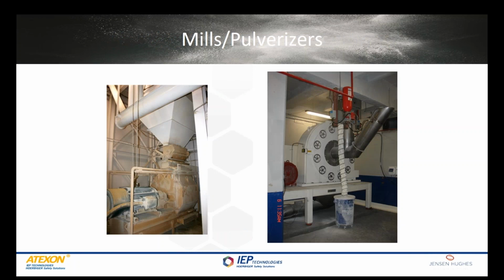Mills, hogs, pulverizers are one of the most common ignition threats that you'll find in a biomass facility. As a result, the risk is not just at the mill itself. You might not have the right dust-air mix for an explosion to occur in the mill itself, but as that product is being conveyed downstream to a receiving vessel, whether by gravity into a hopper or pneumatically to a receiver of some sort, that next interconnected vessel is also at real risk of seeing an explosion. So when you look at the threat around mills, you really want to look at the mill itself, where it's being fed from, any makeup air that may be used to pneumatically transport that product somewhere downstream, and then the next vessel downstream.